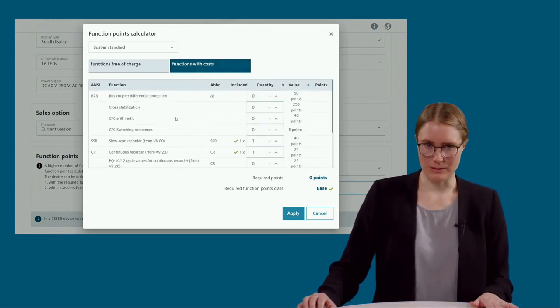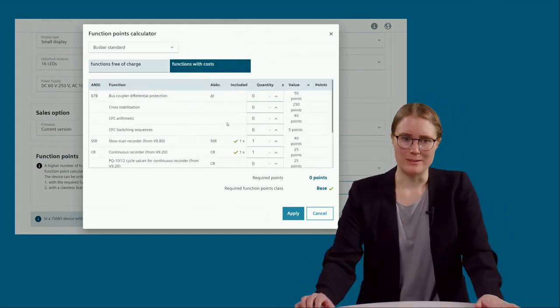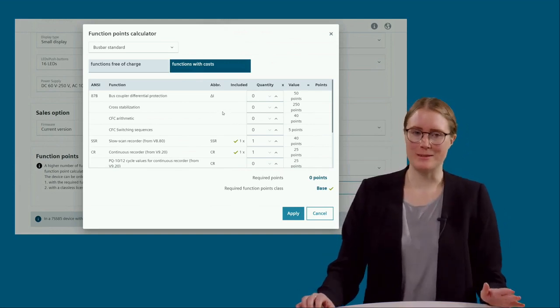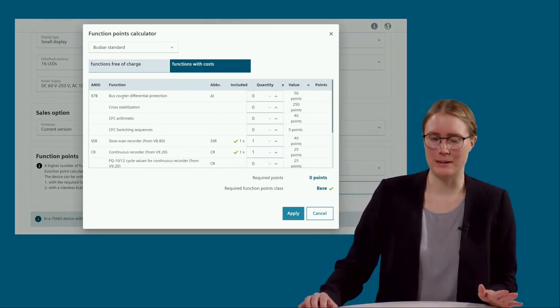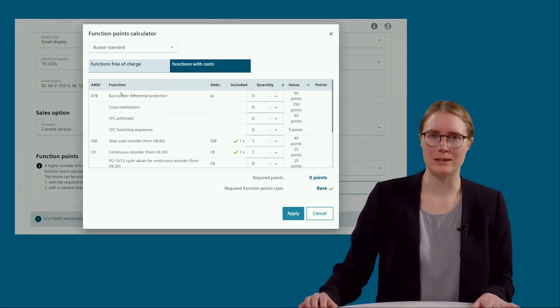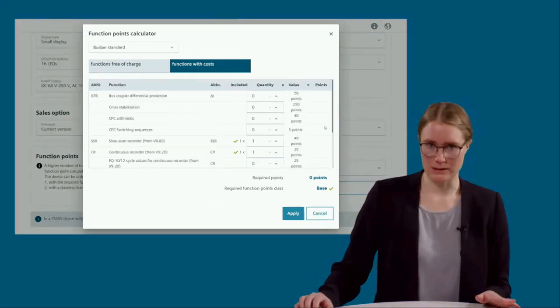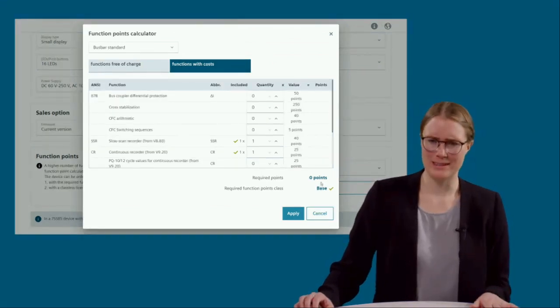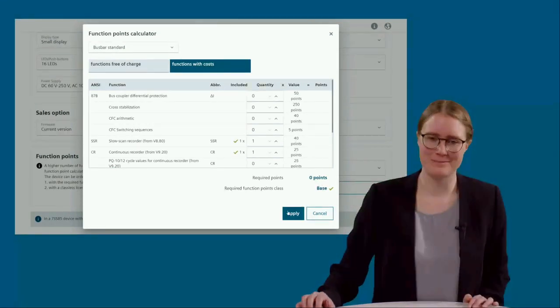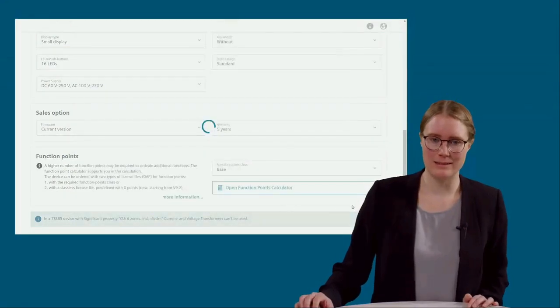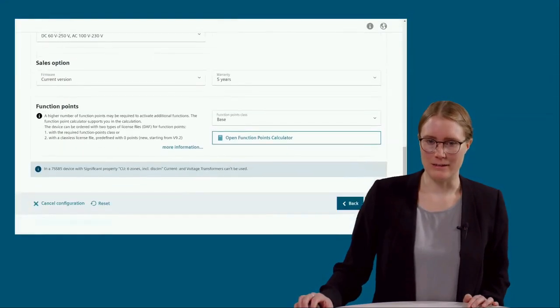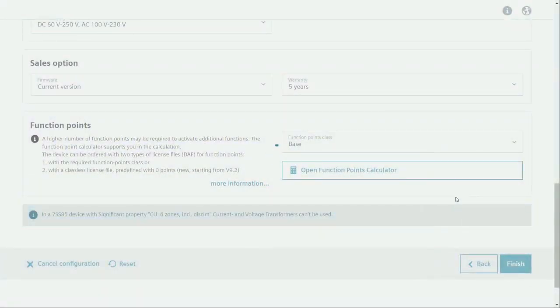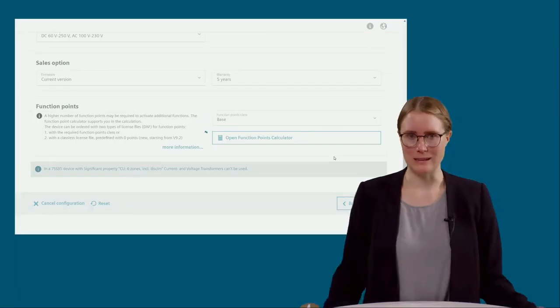So in the function points, there are, of course, some options you can add. Something like, for example, the bus coupler differential protection if you have two CTs in the coupler. But in our case, I will just go with the 0 points. This should be sufficient for our small example. So apply this. And with finish, we have finished our configuration for the central unit of our 7SS85CU solution.